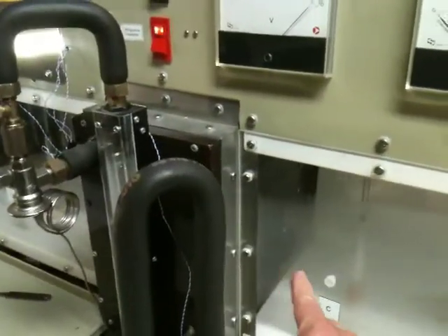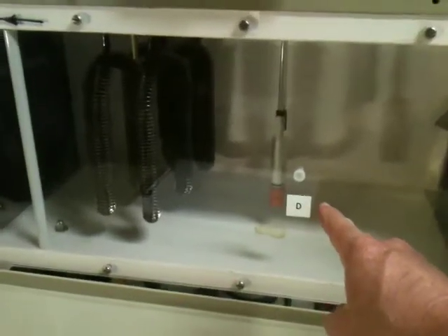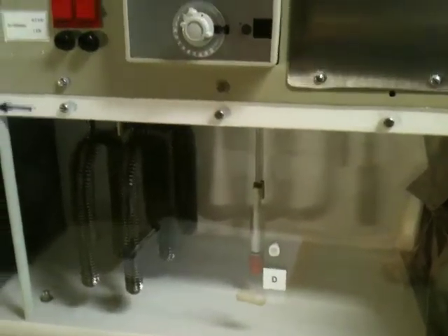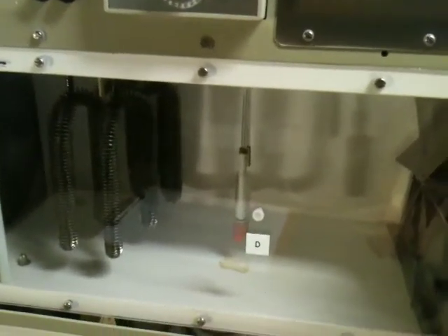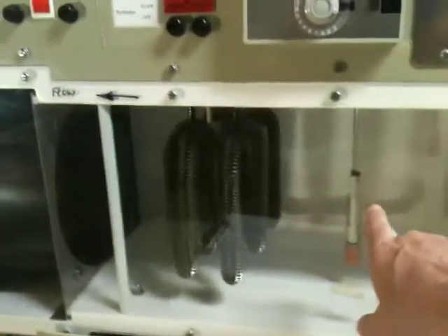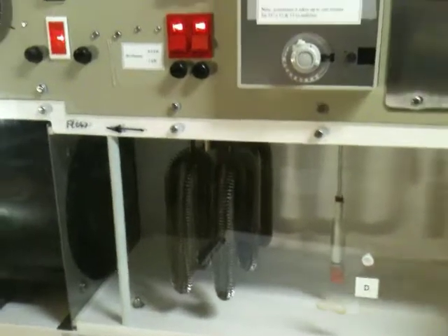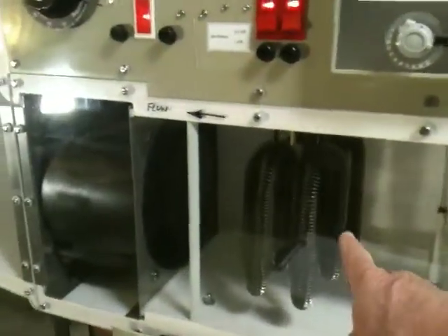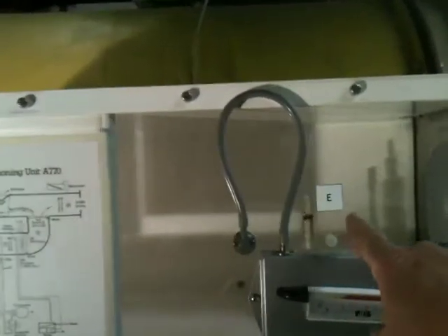The refrigeration unit is right here. Okay, so then station D is downstream from the refrigeration, so that's going to now be cold, moist air, so that's going to bring the two temperatures even closer together. Then here is the reheater. So you see it's fairly close to station D, so there's going to be some radiant heating of the thermocouples at station D, but mostly the reheater is going to heat the air, which travels through the fan, up the backside here, and over to station E.